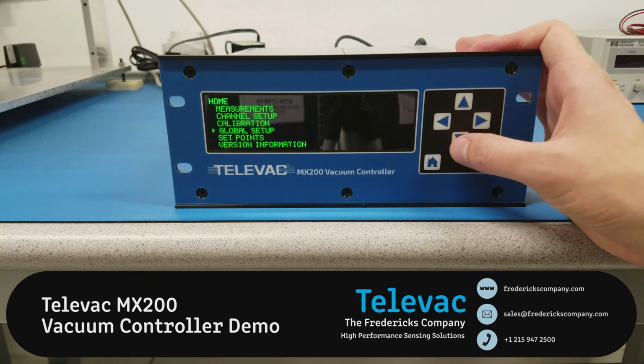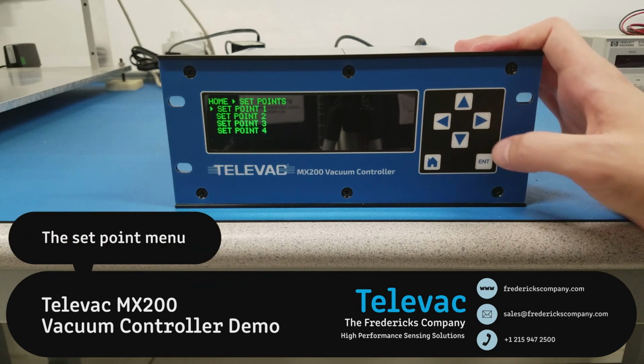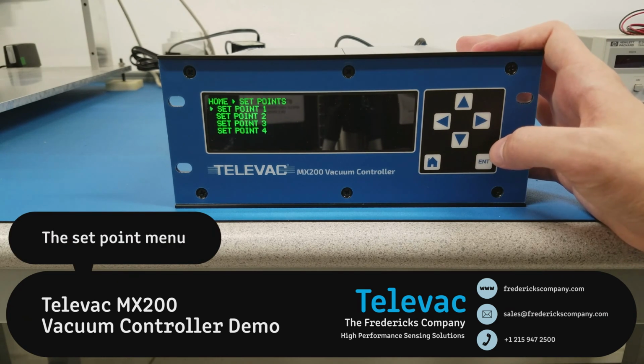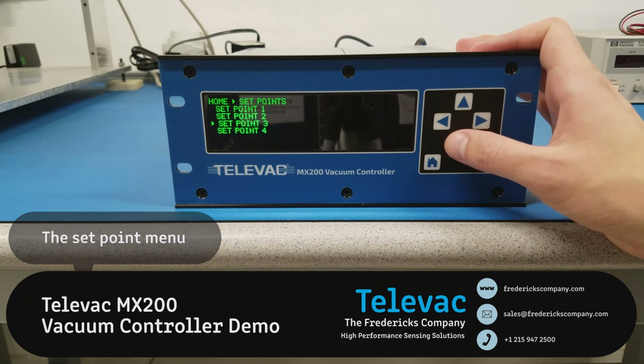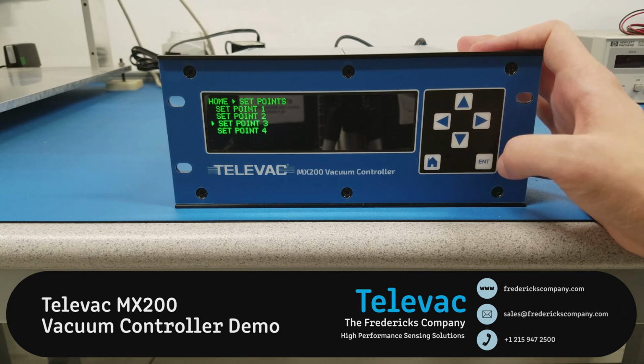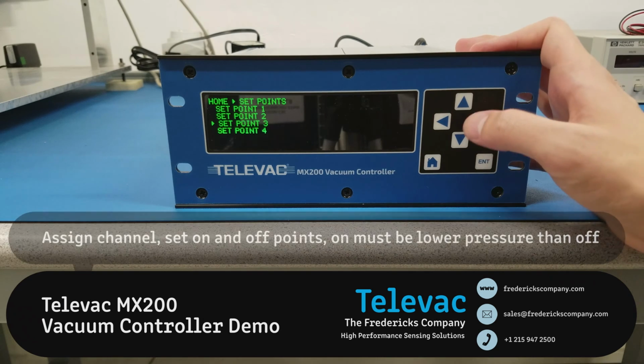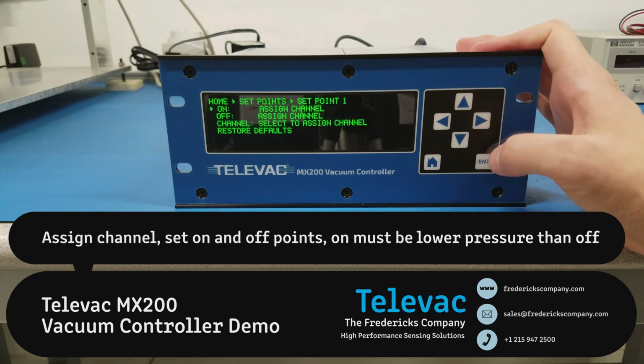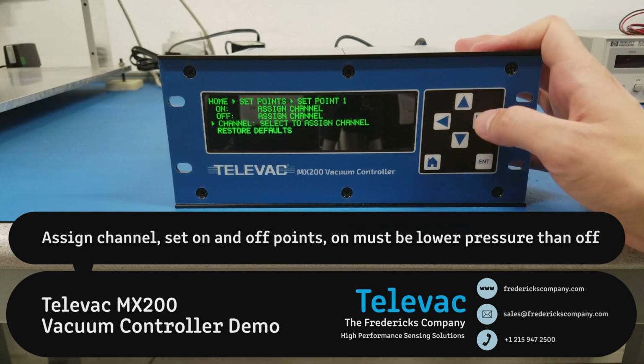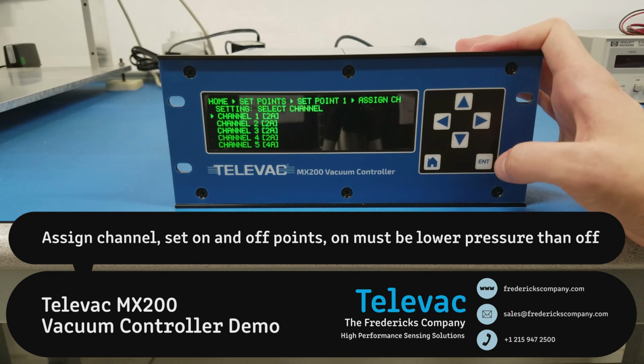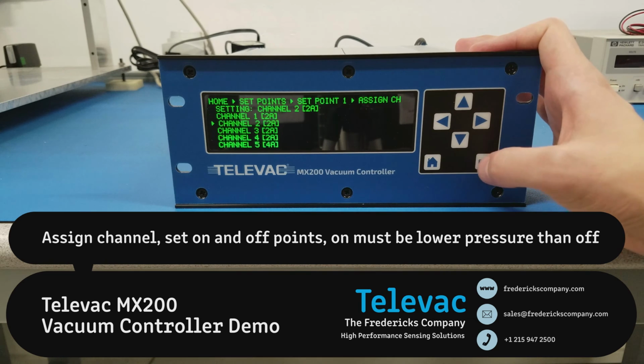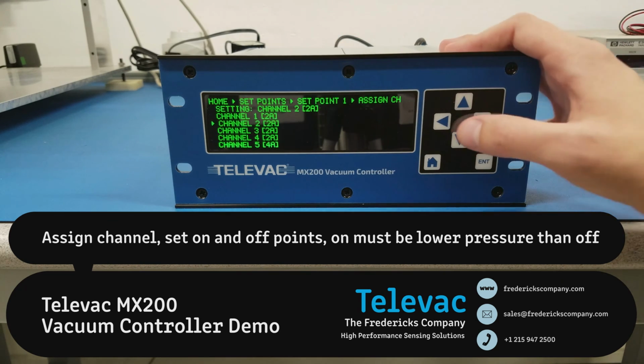So the last menu that we'll look at is the set points. This unit has a single relay set point board attached to it, so there are 4 set points available. You can go in, first you have to assign a channel to it. So let's select channel 2 for example. So now channel 2 is saved for set point 1.